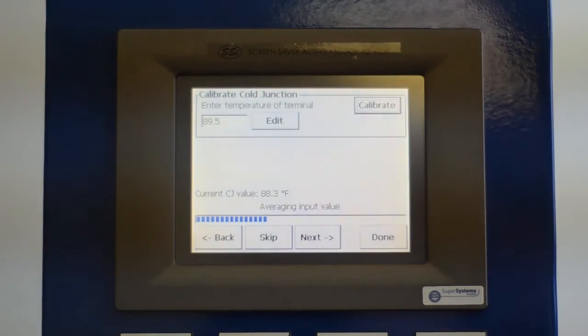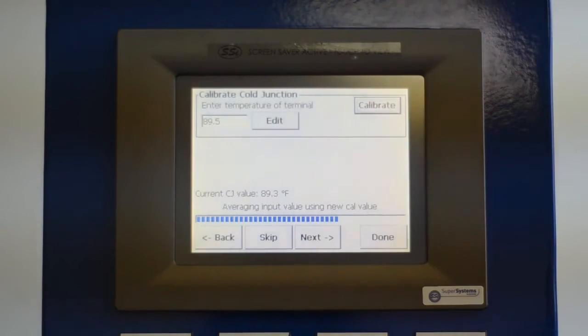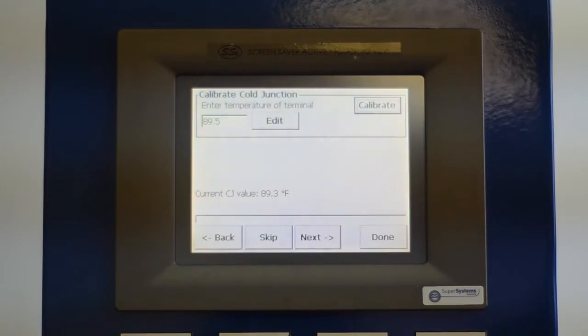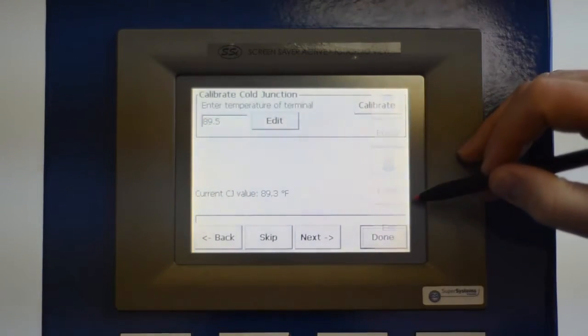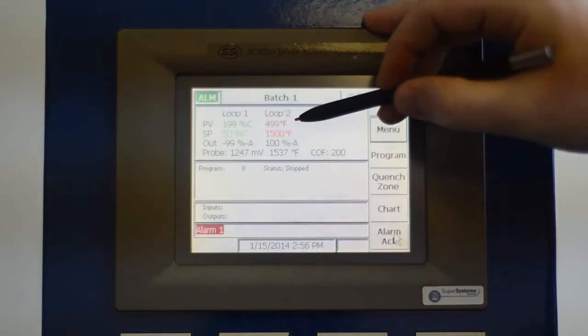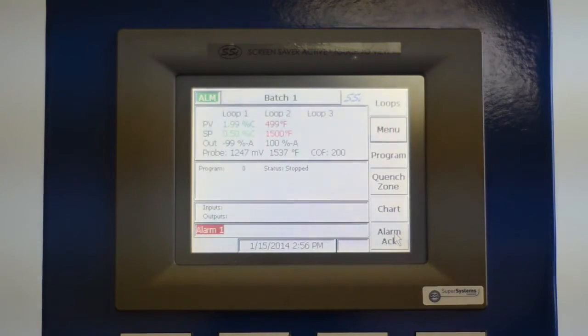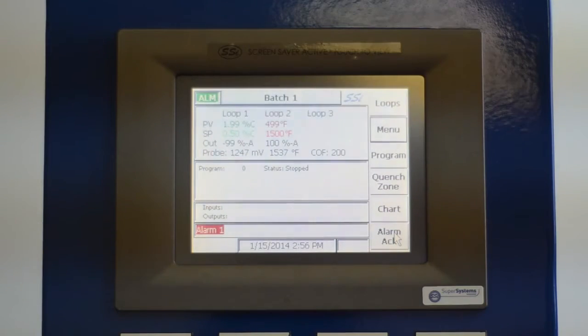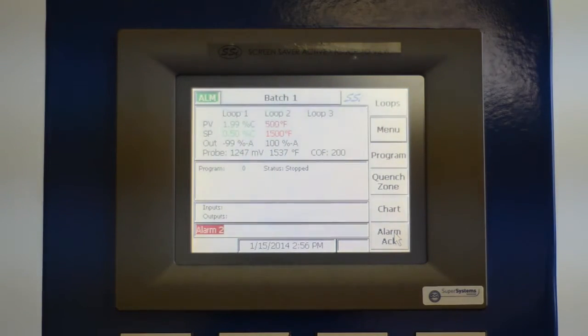With the first generation screen, you do have to give it a slight amount of time for the delay between the communications of the screen and the controller. So once complete, select done and escape back to our main menu, and then we should see our temperature now. We're sourcing in 500. We'll take a second for it to register the adjustment, and then we should see it now reading 500.